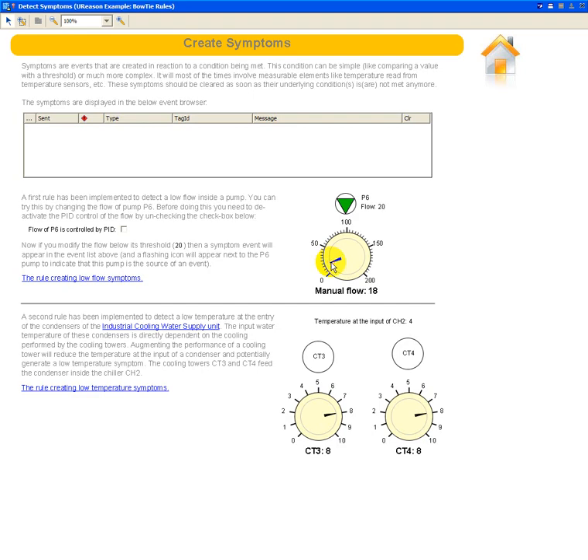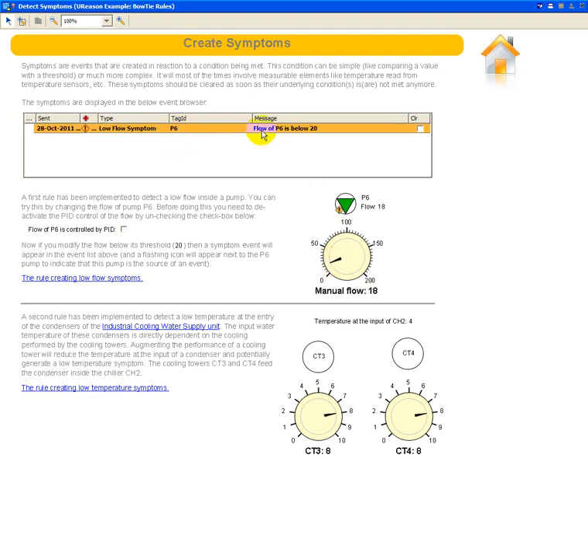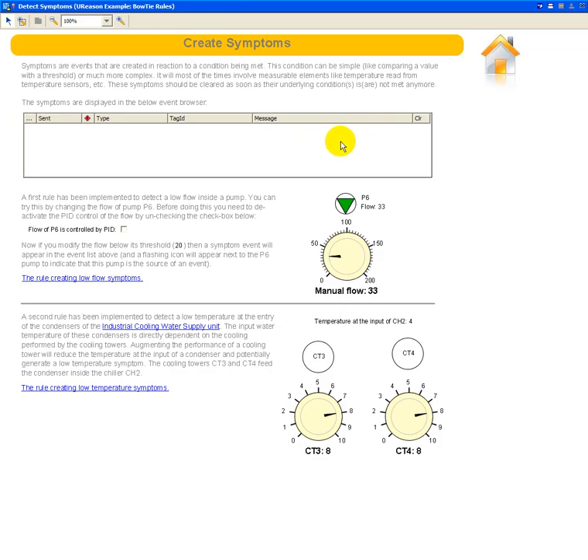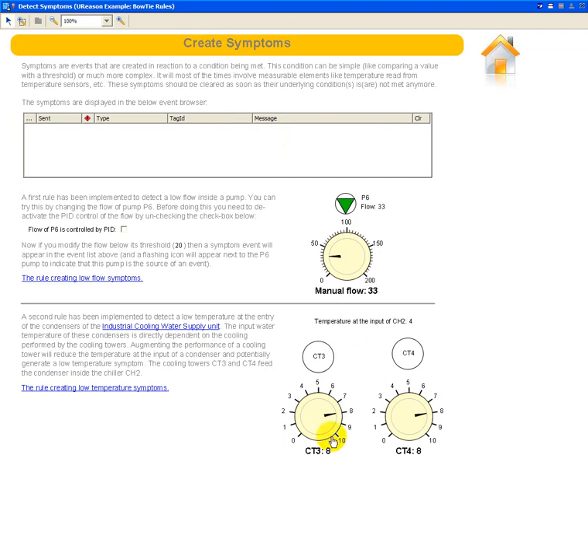So if I go below, it will generate an event to indicate that the flow of P6 is below its threshold, and a little icon appears here. If I control again this value and set it back to a value higher than 20, the event is cleared and disappears from my event browser here. The same would be valid for these cooling towers, but I will not demonstrate that right now.